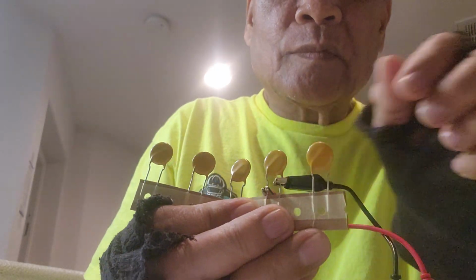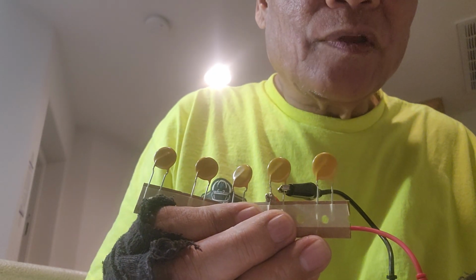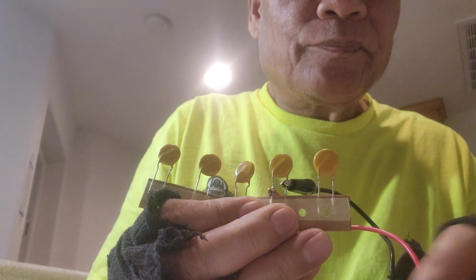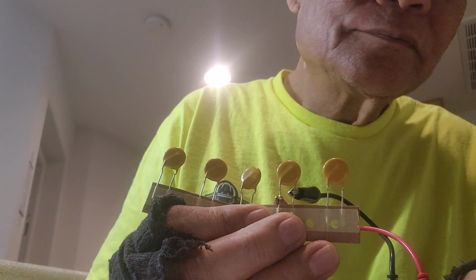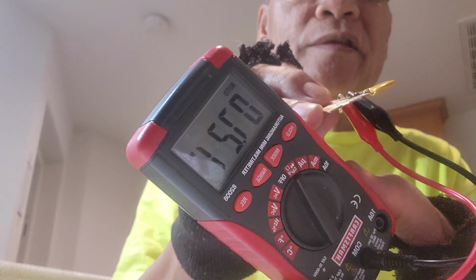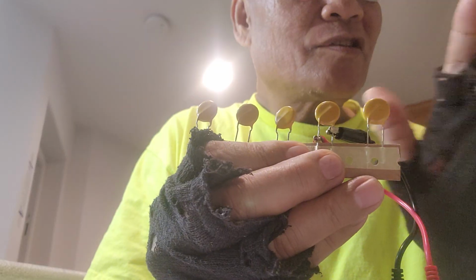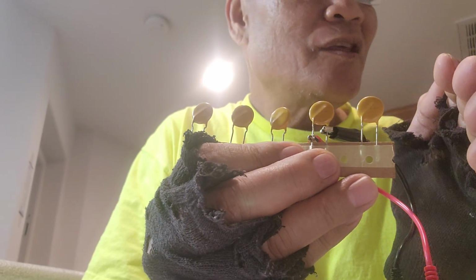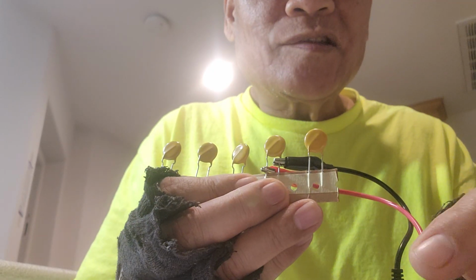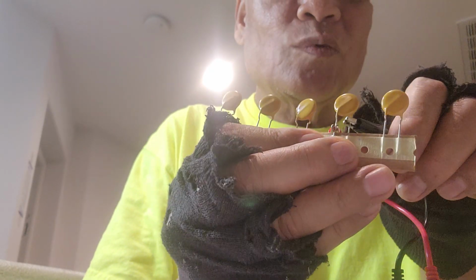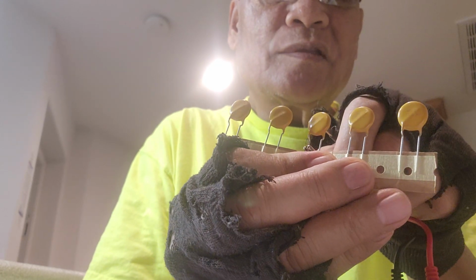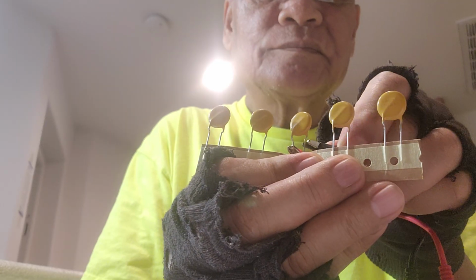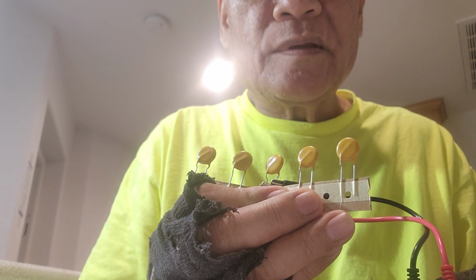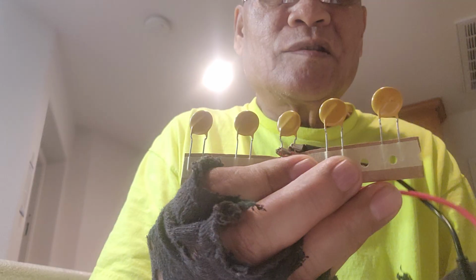It got a reading, and it's not a small one. It's in the million ohms range, around 7 million ohms. That's fine, as long as the reading is in the million range. This second one is actually 8 million ohms. Let me check the third one. Oh, this is bigger, 11 million ohms. So that's fine too.